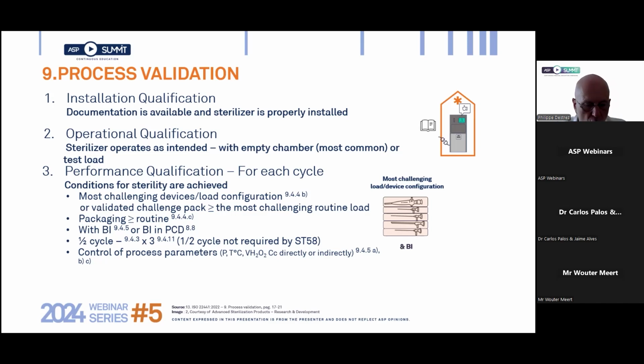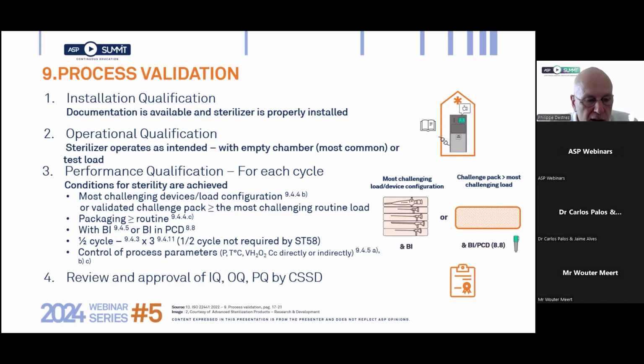Two approaches are possible. One is for the healthcare facility to select the most challenging load and device combination. But since real devices cannot be contaminated for obvious reasons, the spores are placed in or around the load. The second option consists in using a challenge test pack, which is validated to represent the most challenging load. This challenge test pack is used in combination with a PCD, a process challenge device, that, as explained in paragraph 8 of 22441, simulates a device with a 6-log spore inoculum at the most difficult location in that medical device. But all these operations, even if they are not performed by the healthcare facility, are under its responsibility and need to be reviewed and approved by the sterilization department. Next slide.